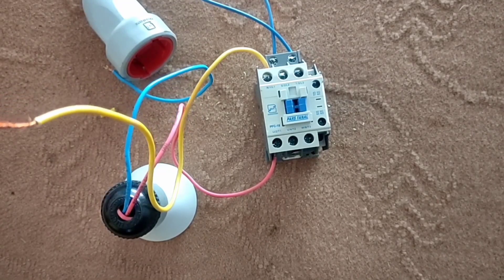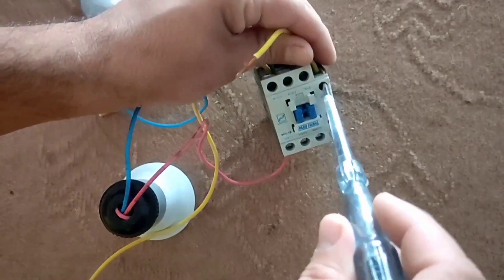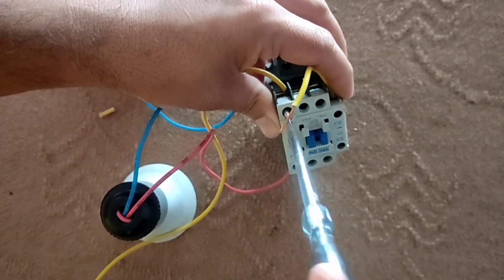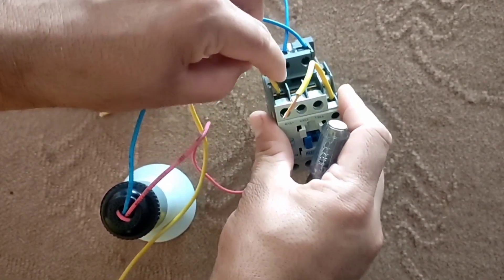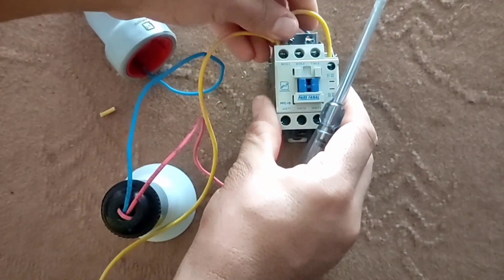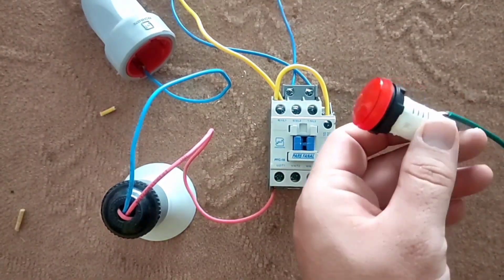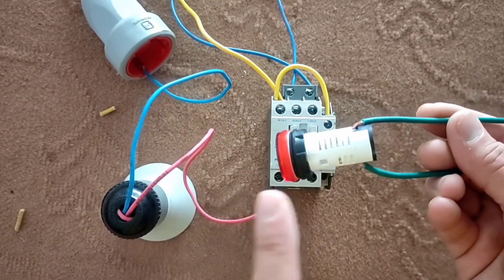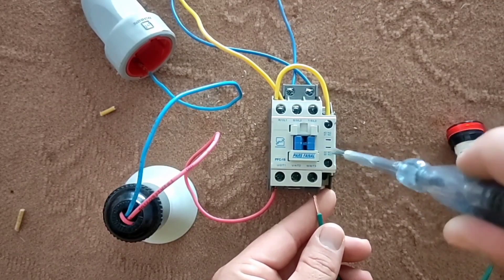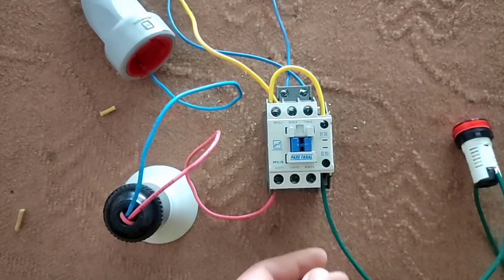Now we want to connect the error lamp. For this we connect a phase wire to the input of the normally closed blade. The error light has a phase wire and a null wire like a normal lamp — we want it to turn off when the main lamp is on, and vice versa. For this we connect the phase wire of the error lamp to the normally closed blade terminal and connect the null wire directly.